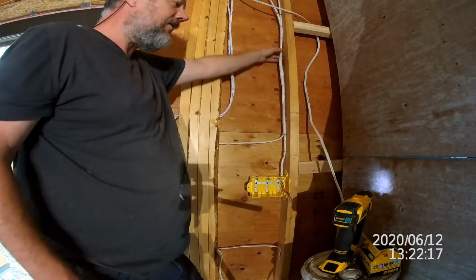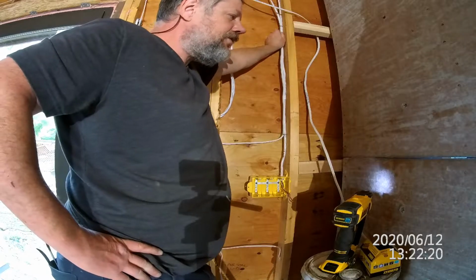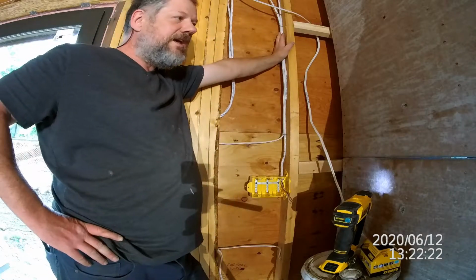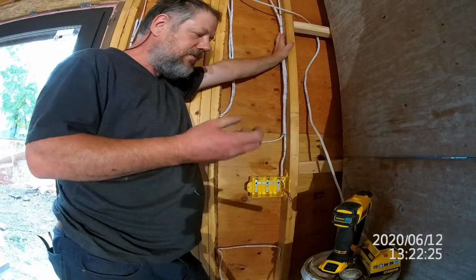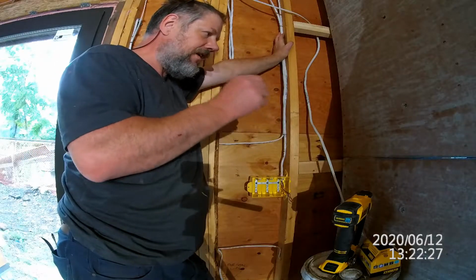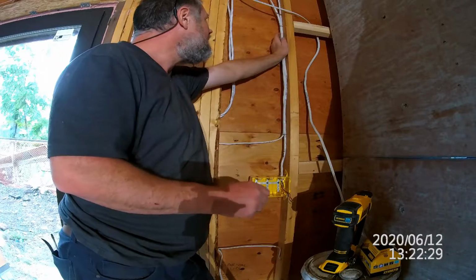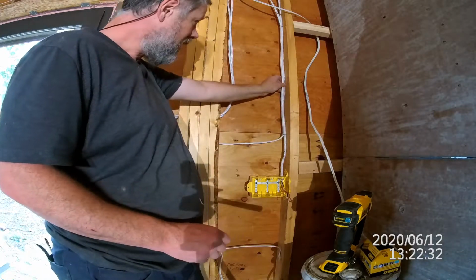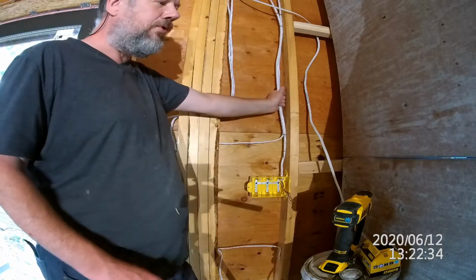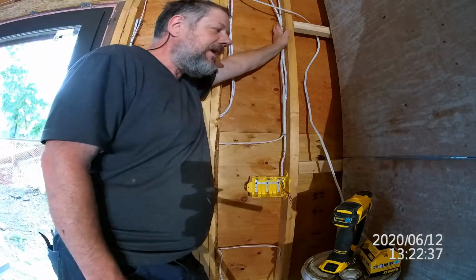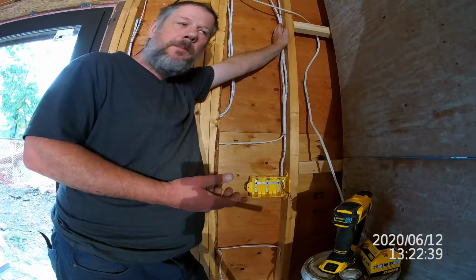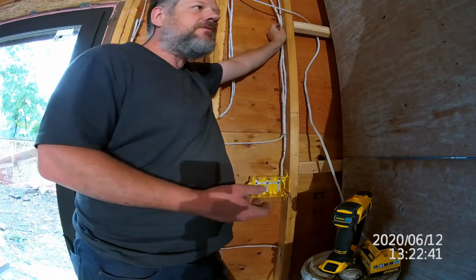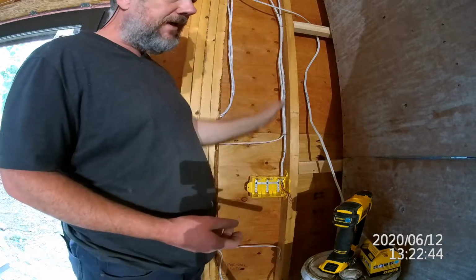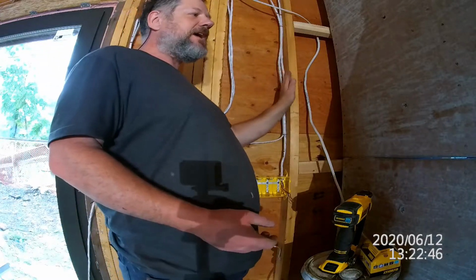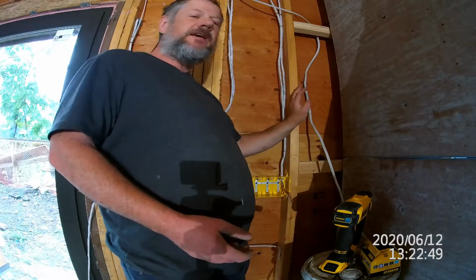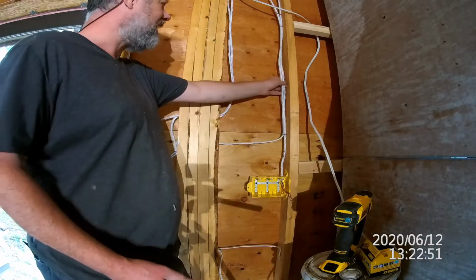Now the reason you want it to move - there's two reasons. One is, as I said, you don't want a stress riser created, you don't want to overly compress that copper inside the conductor. But you also want flexibility. The whole point of the staple is to hold the cable in the general location in the stud bay so that it's free from mechanical damage of things being attached to the wall on each side.